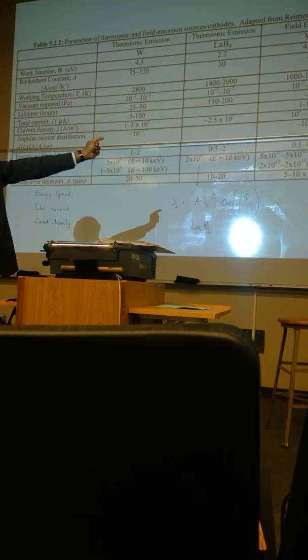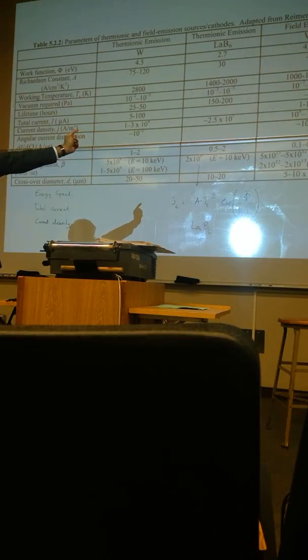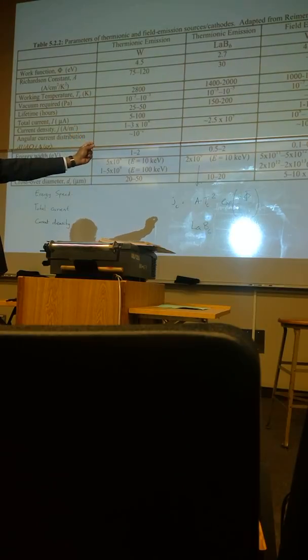That's actually an important factor because we are doing cold emission, we need higher vacuum. So all the costs start to go up because you have to go from a typical 10^-7 torr to two orders of magnitude higher vacuum. Then of course the whole thing becomes much more expensive. Then the lifetime, of course the filament lifetime is also an important thing. When you heat it up to such high temperatures, the filament doesn't last very long. In the old days, 30 or 40 years ago, when people were working with microscopes, you would always be taking out the gun and changing the filament every week at least. Now you don't do that.